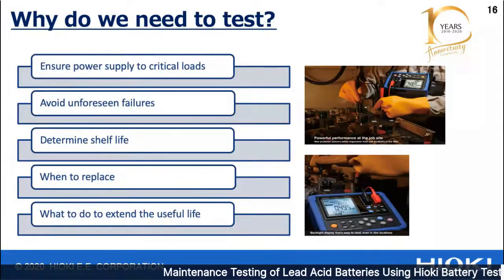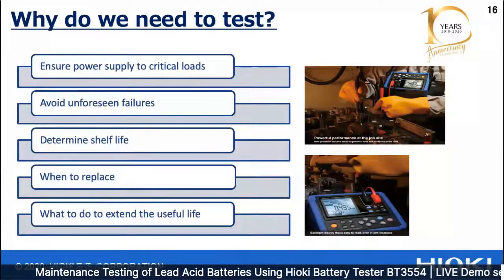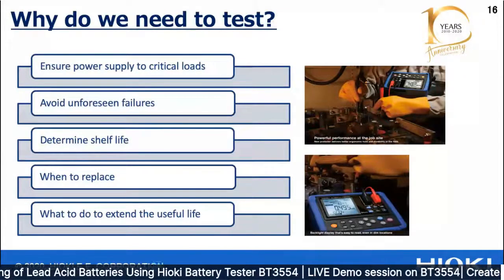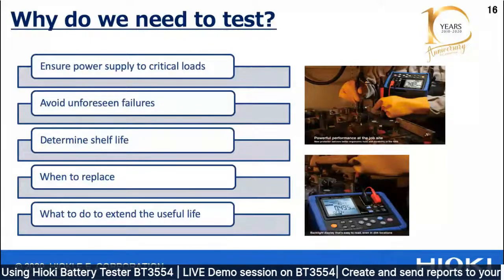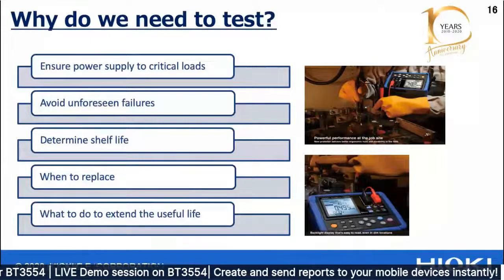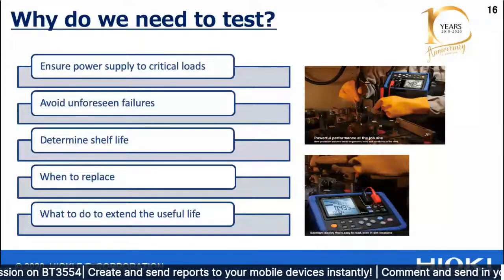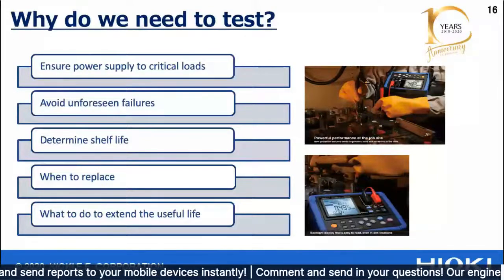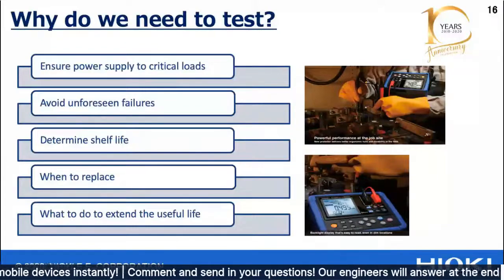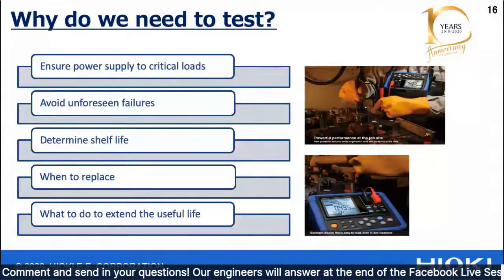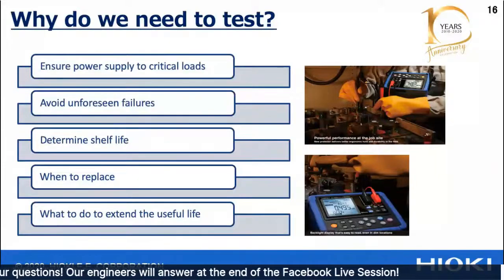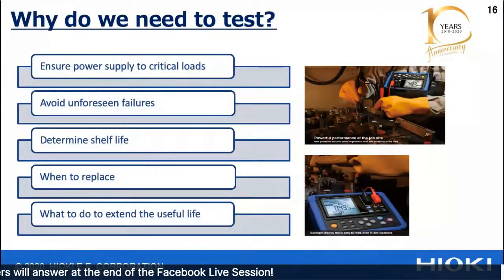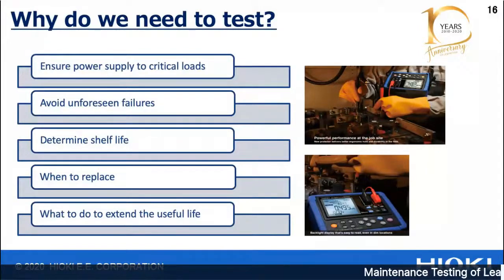Companies need to know how to extend battery life and find the optimal replacement time. To keep a lead acid battery in good condition, apply a fully saturated charge lasting 14 to 16 hours. If the charge cycle doesn't allow this, give the battery a fully saturated charge once every few weeks. If possible, operate at moderate temperature and avoid deep discharge. So charge as often as you can - that's one way to extend the useful life of the battery.